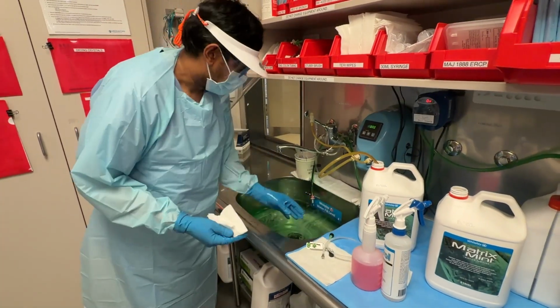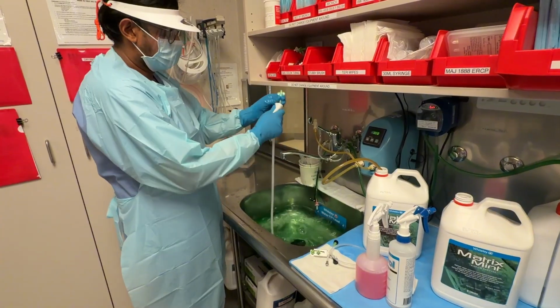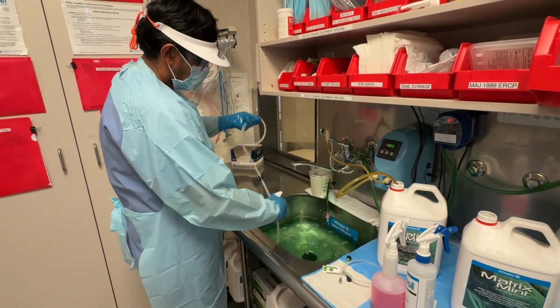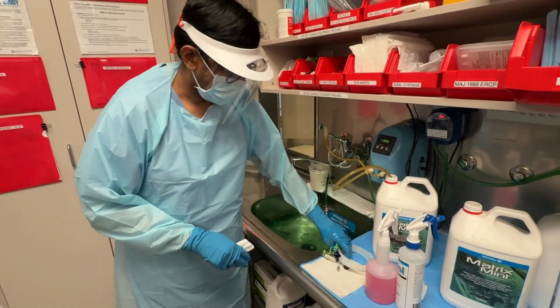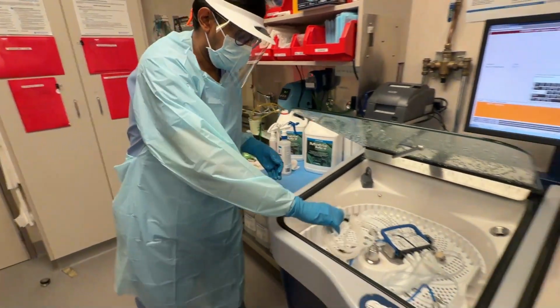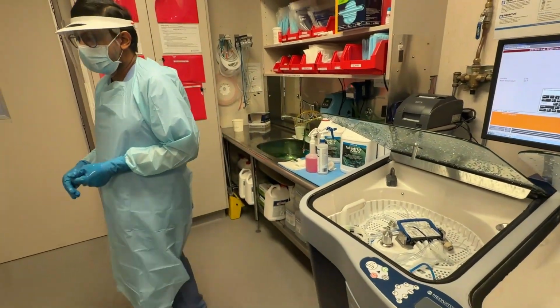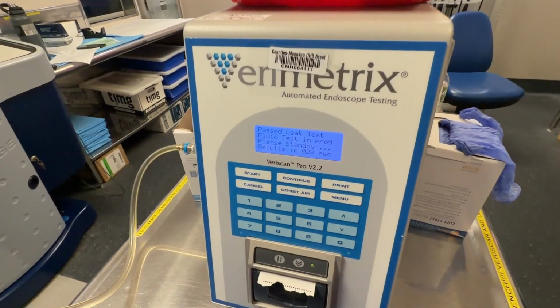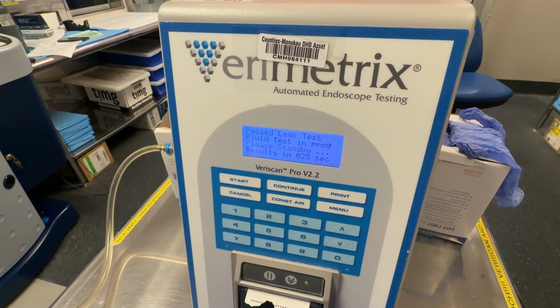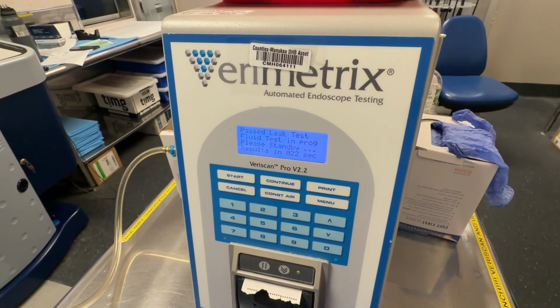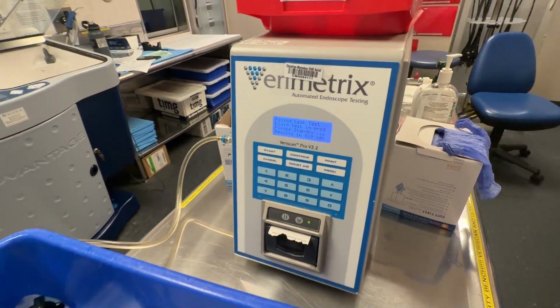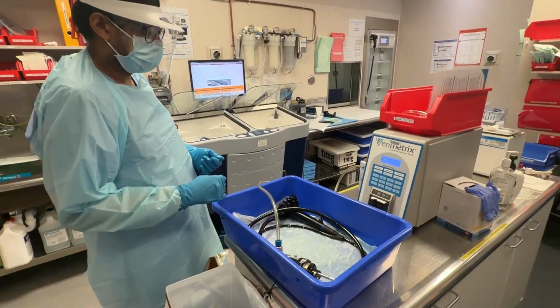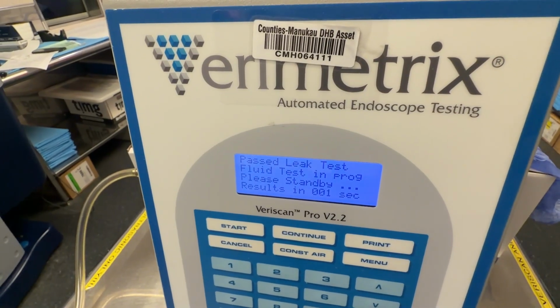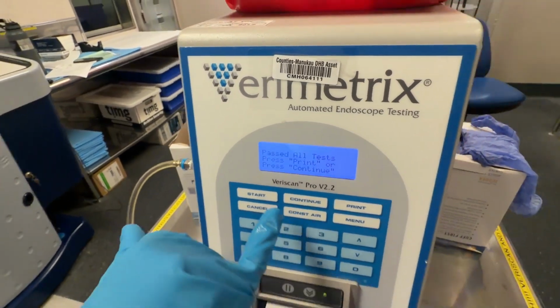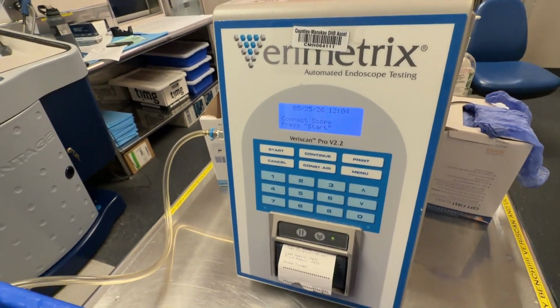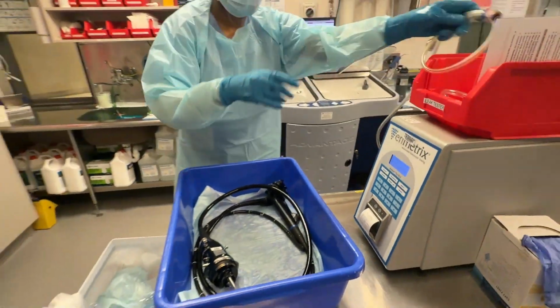So if the scope passes, we will take the scope to the sink, and we will do the brushing later. And if the scope does not pass during the testing, we will put the scope inside the basin, and we will connect the machine, and we will flush air through the connection to find out where the leakage has happened. So if we find a leakage, we will stop the reprocessing, and the scope will be sent for repair.